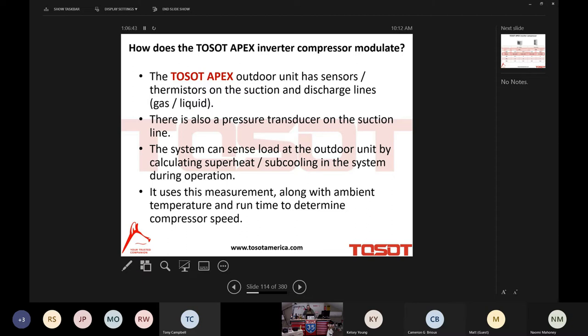Isn't that beautiful? Again, not as perfect, I will say, as the mini split product, because there is a direct communication between the indoor and outdoor unit in the mini split product. The Apex, we wanted to, I should say, wait, I wish it was me. Tosot wanted to design the outdoor unit to be a universal replacement. Don't need to connect it with our indoor unit. So that's why there's less communication potential between the indoor and outdoor unit.